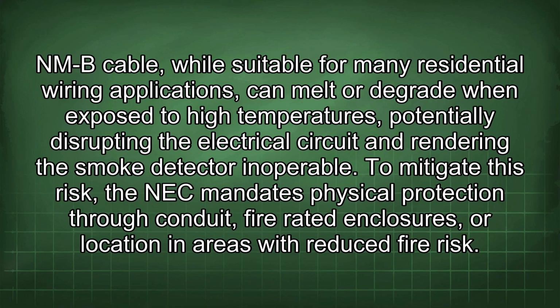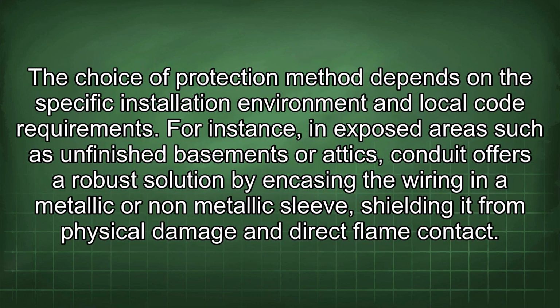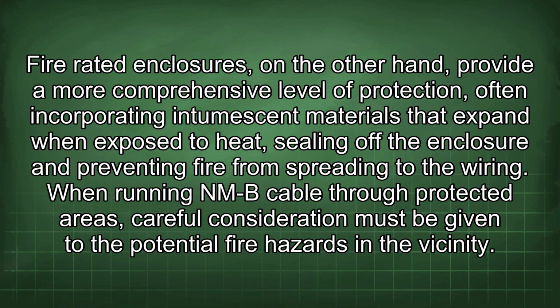To mitigate this risk, the NEC mandates physical protection through conduit, fire-rated enclosures, or location in areas with reduced fire risk. The choice of protection method depends on the specific installation environment and local code requirements. For instance, in exposed areas such as unfinished basements or attics, conduit offers a robust solution by encasing the wiring in a metallic or non-metallic sleeve, shielding it from physical damage and direct flame contact. Fire-rated enclosures, on the other hand, provide a more comprehensive level of protection, often incorporating intumescent materials that expand when exposed to heat, sealing off the enclosure and preventing fire from spreading to the wiring.